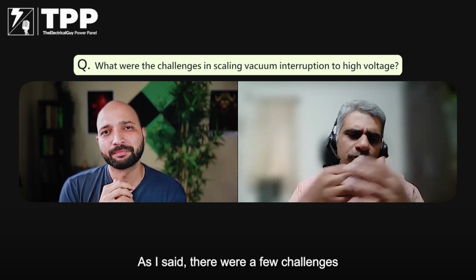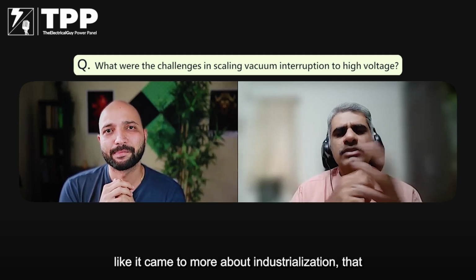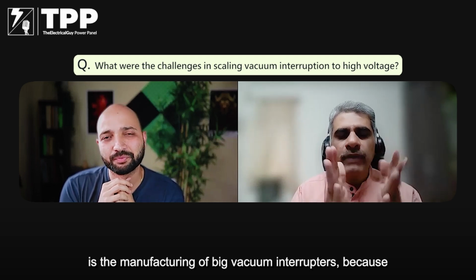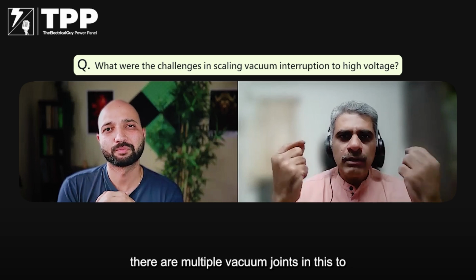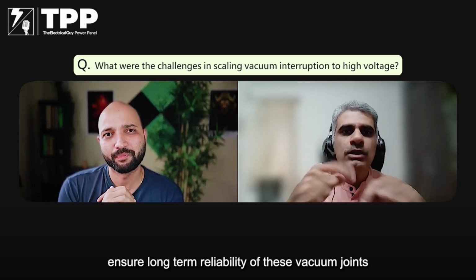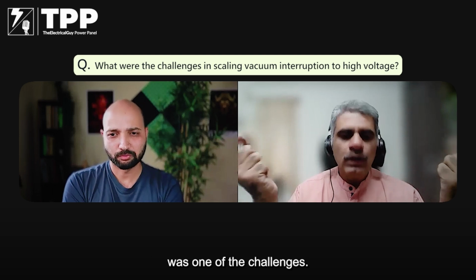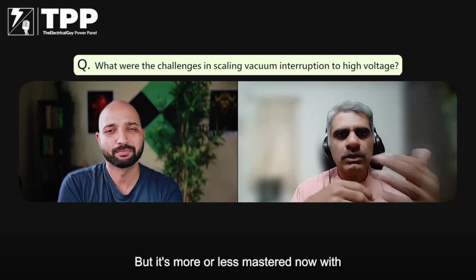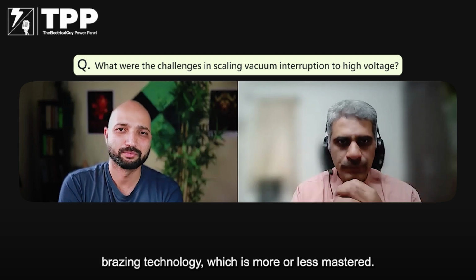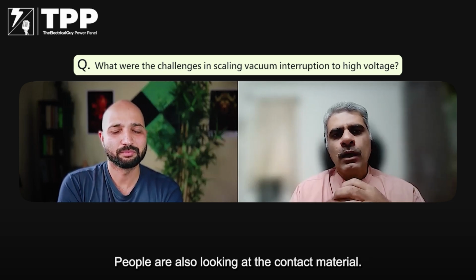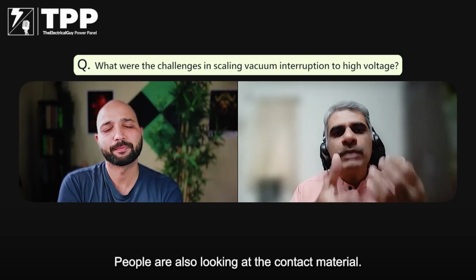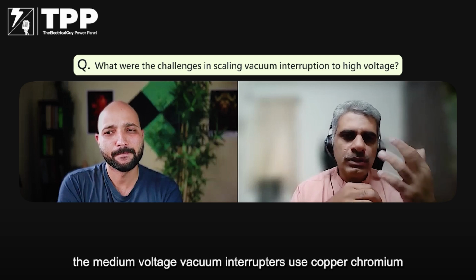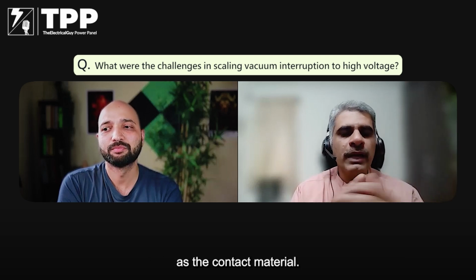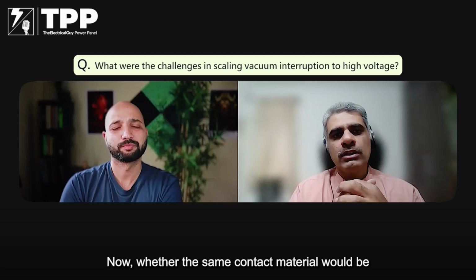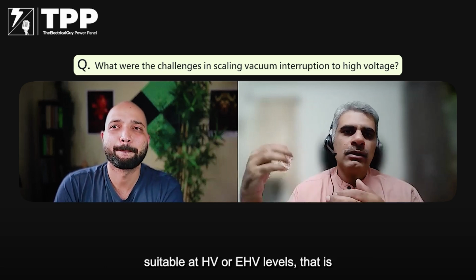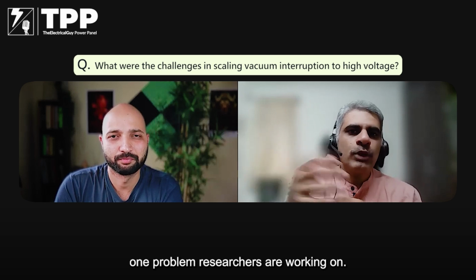Yes, as I said, there were a few challenges. It came down to industrialization, that is, the manufacturing of big vacuum interrupters, because there are multiple vacuum joints in this. Ensuring long-term reliability of these vacuum joints was one of the challenges, but it is more or less mastered now with a lot of research and development on brazing technology. People are also looking at the contact material. In medium voltage, I forgot to mention, vacuum interrupters use copper chromium as the contact material. Now, whether the same contact material would be suitable at HV or EHV levels is one problem researchers are working on.